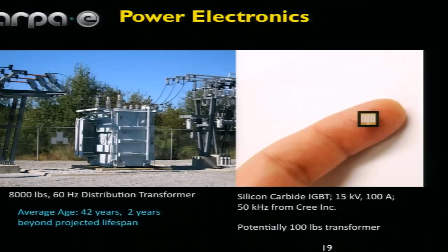So we thought maybe there's a better way than just replacing old transformers with the same design. We created a program in power electronics using wide bandgap semiconductors like silicon carbide or gallium nitride. Here's a single transistor, a silicon carbide IGBT, that handles about 15 kilovolts and 100 amps—1.5 megawatts on something the size of a fingertip. This is now the heart of the integrated circuit of this device.